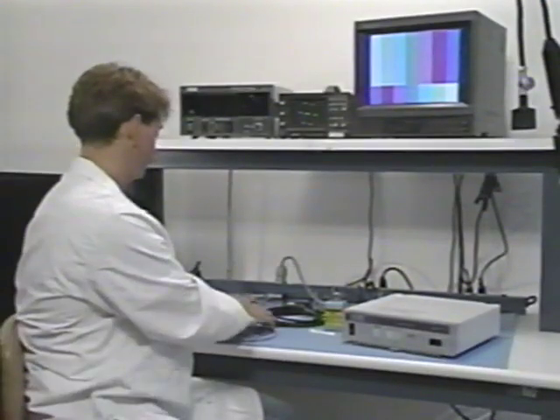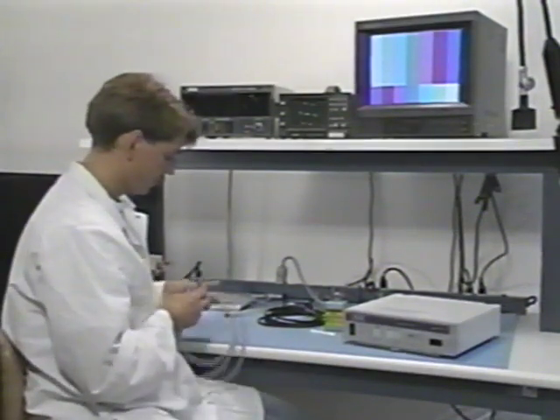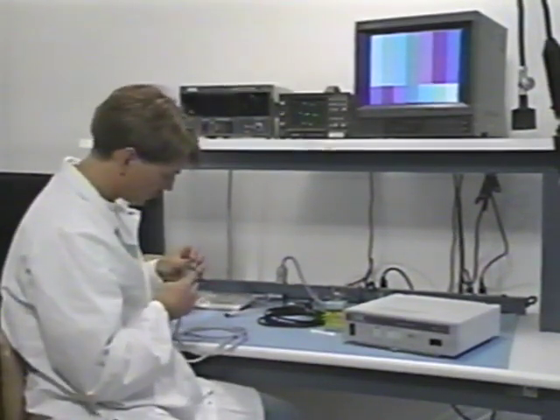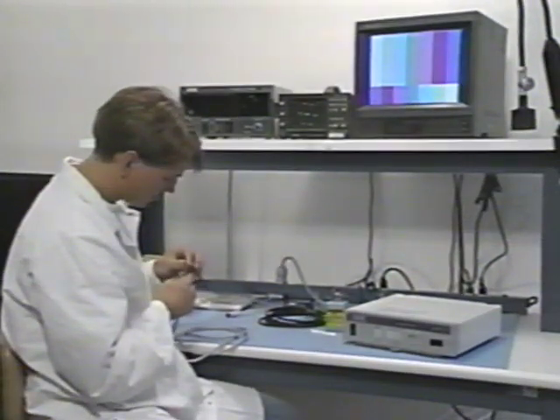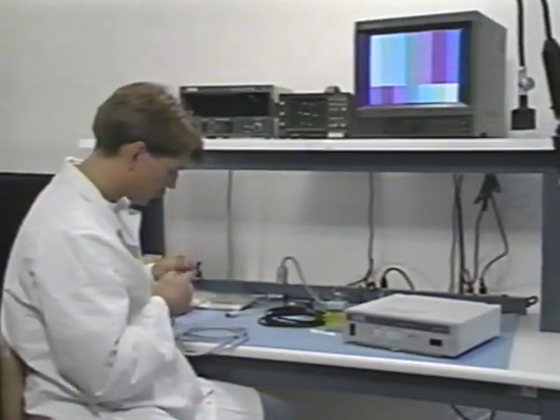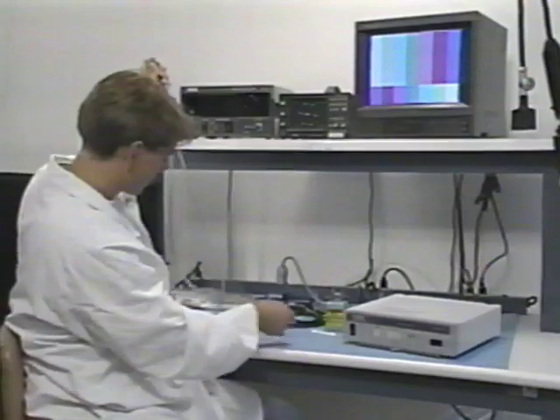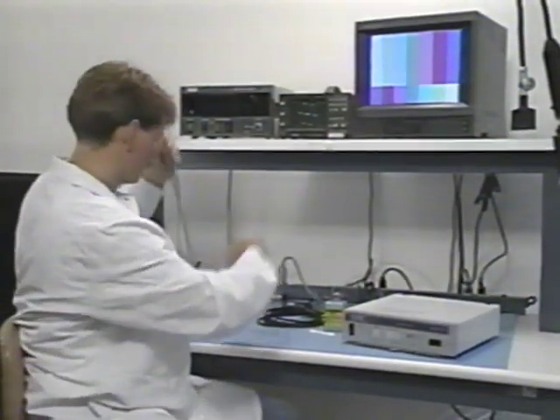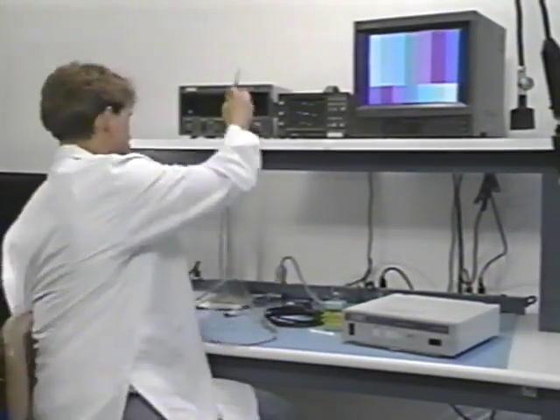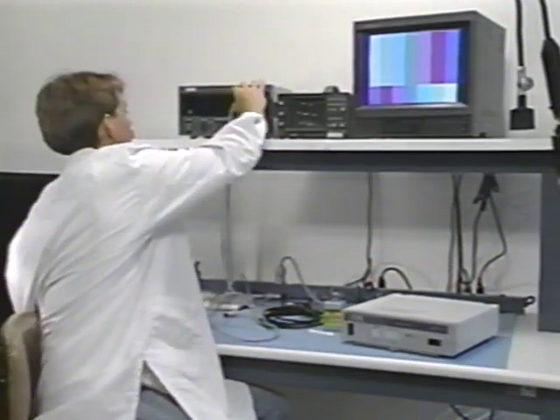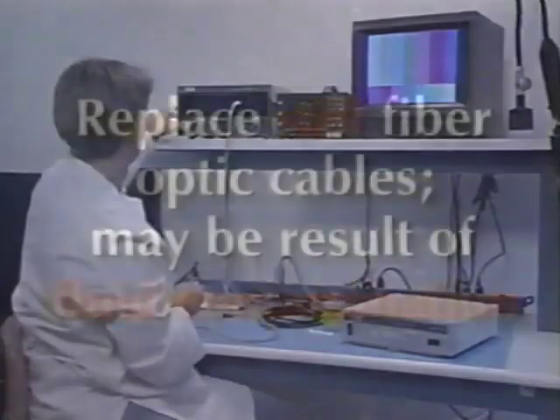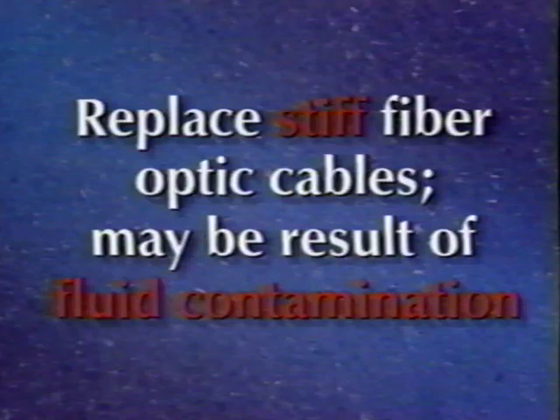The way to check a fiber optic light cable is to look at the end of the cable which attaches to the scope. It should be clear of broken fibers or black dots. A few broken fibers have a minor effect on the transmission of light, but when 1/3 or more of the fibers are broken, it is time for a new light guide cable. Stiff fiber optic cables should be replaced. This is a symptom of fluid contamination.